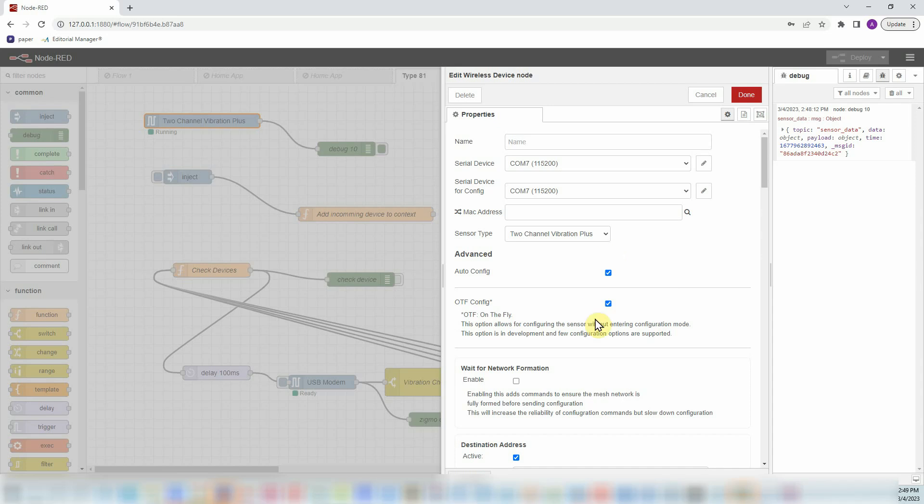Autoconfig and OTF config: if you have selected both of these, it means that every hour the vibration sensor sends a command called FLY. It means like hey, I'm gonna stay awake for a few seconds, and during this time you can send me all the new settings or if you want to change anything in my settings, send me those commands.